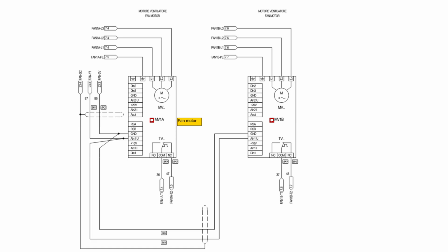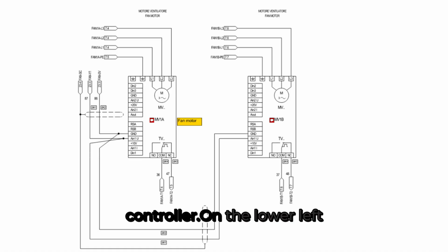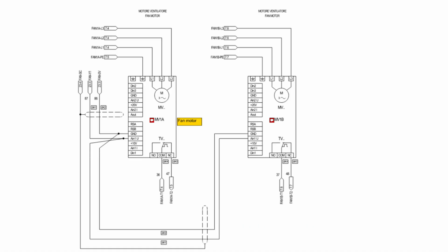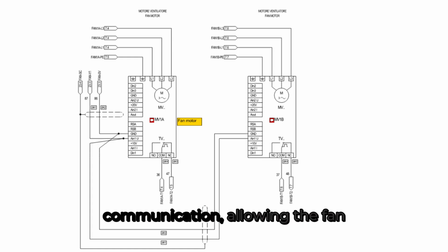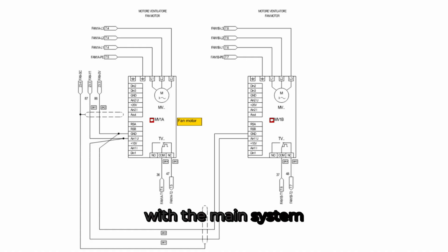In the control board of the fan, AN1 and AN2 are analog inputs that receive a 0 to 10 volt control signal from the controller. On the lower left side, you'll see RSA and RSB terminals. These are for RS-485 communication, allowing the fan motor controller to communicate with the main system controller. Each fan also has a thermal protection sensor, shown as TV1 and TV2, wired into the control system to detect overheating and shut down the motor if needed.